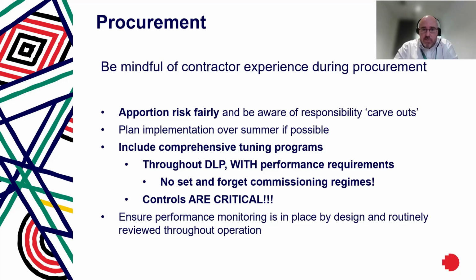Of course, you want to try and manage your implementations over summer and not over the winter months, if you can. And you want to include comprehensive tuning programs. So throughout the defects liability period, you want to have performance requirements. You can't just set and forget with a commissioning regime on practical completion. You need the controls to be constantly evaluated, especially in the first thermal cycle, 1 year, and optimized. Ideally, you want to have that program in place throughout the entire year.